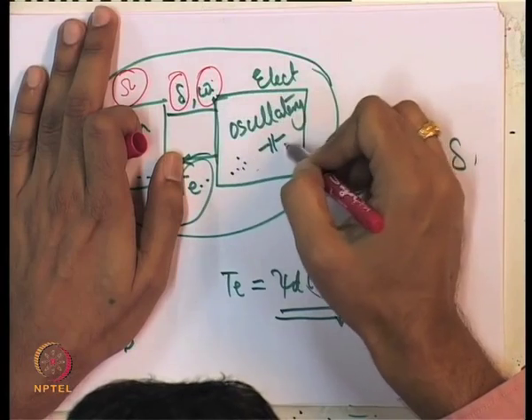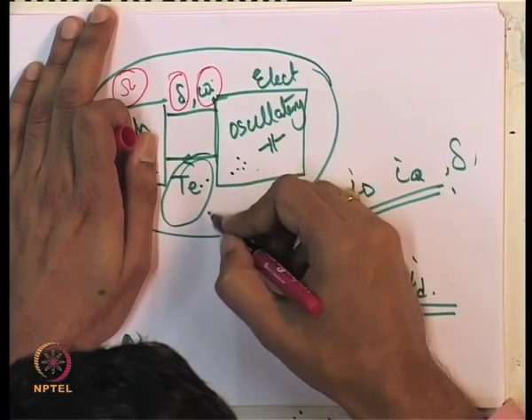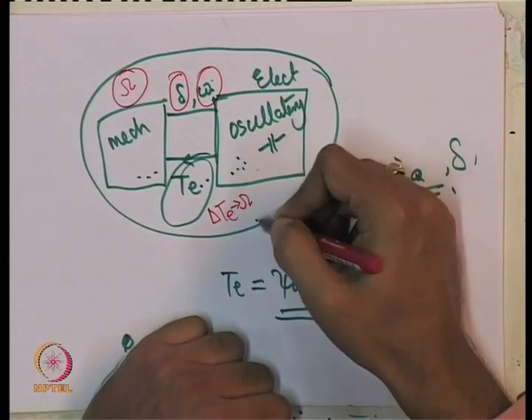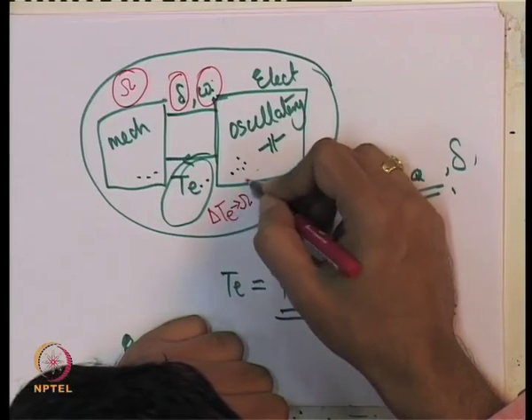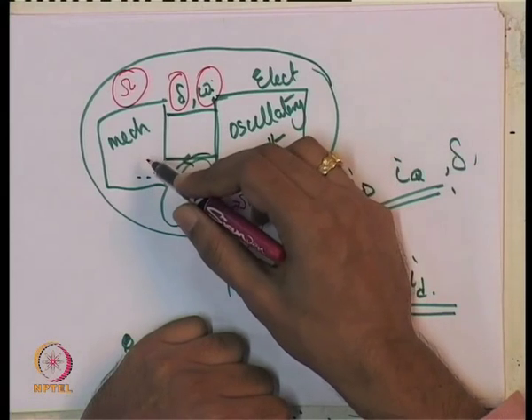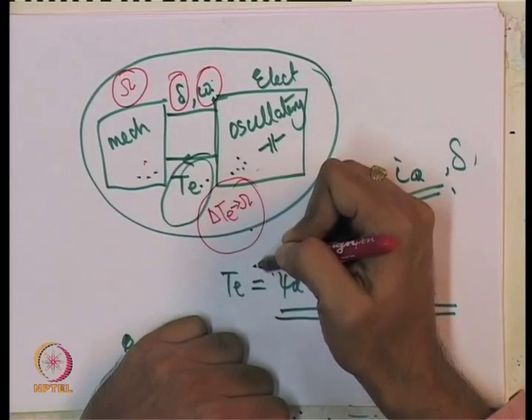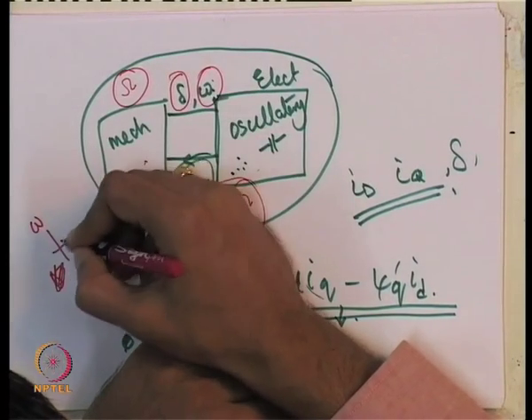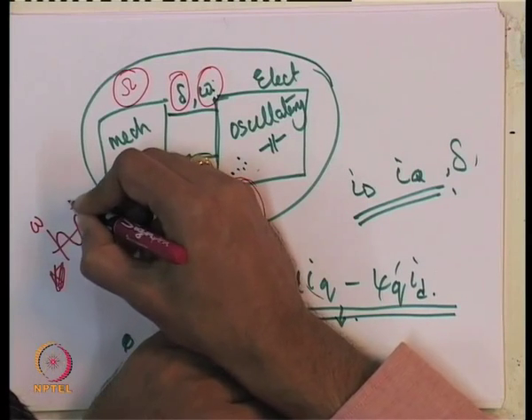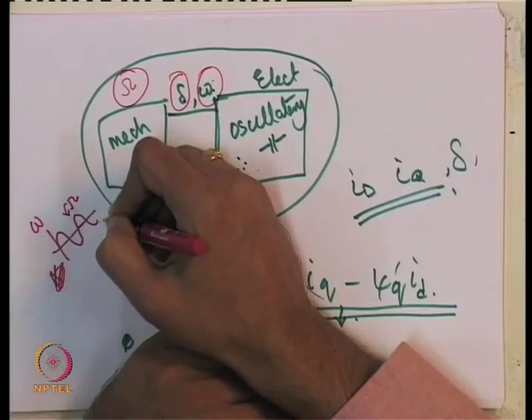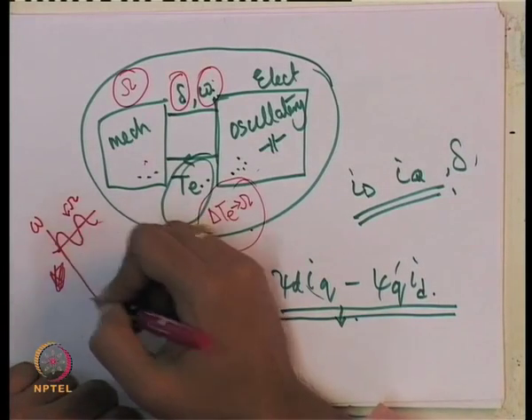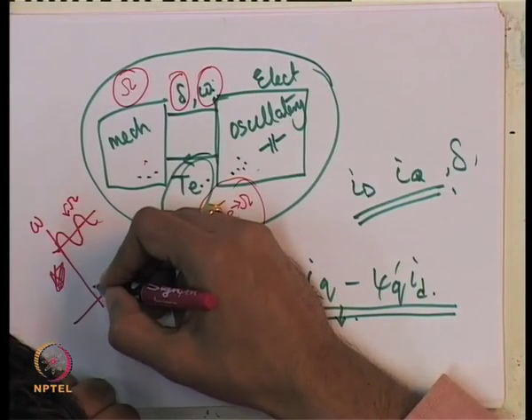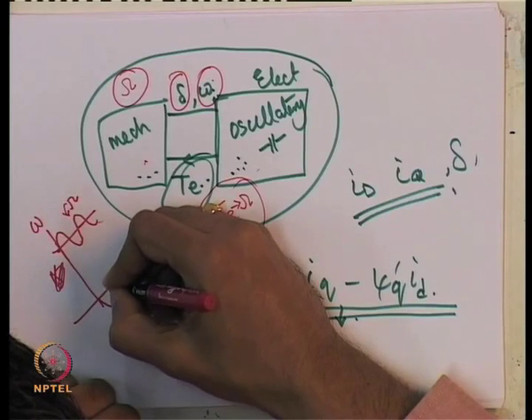The point which is very important: when the electrical and mechanical system interact with each other, you can do the eigenvalue analysis of the mechanical and electrical system put together. But before doing that, let us have some insight: what will happen in case the mechanical oscillatory frequency becomes close to or equal to the oscillatory frequency of the electrical network? Let us look at it in a cause-and-effect manner — this is called damping torque analysis.